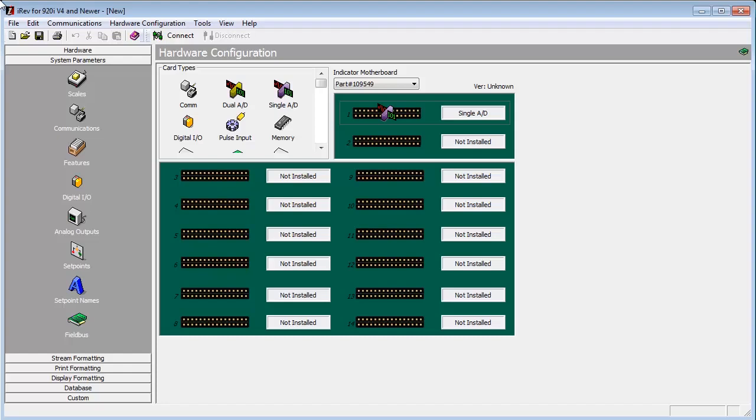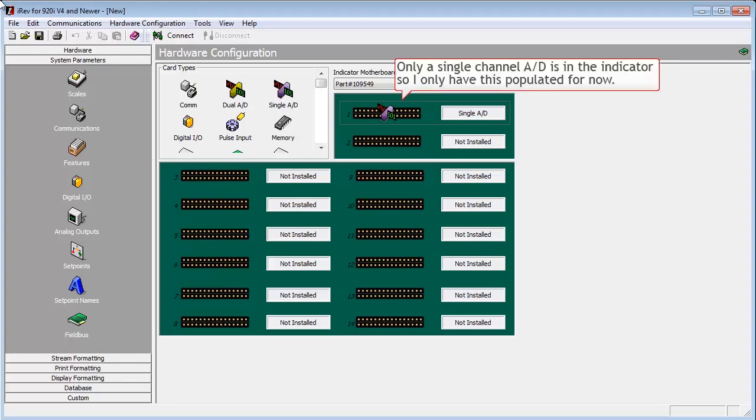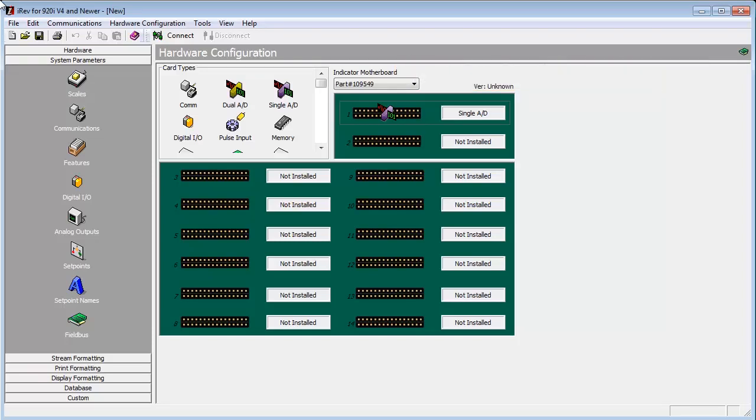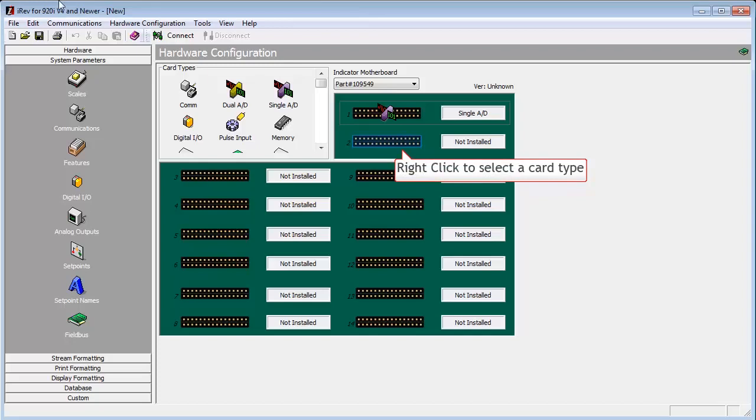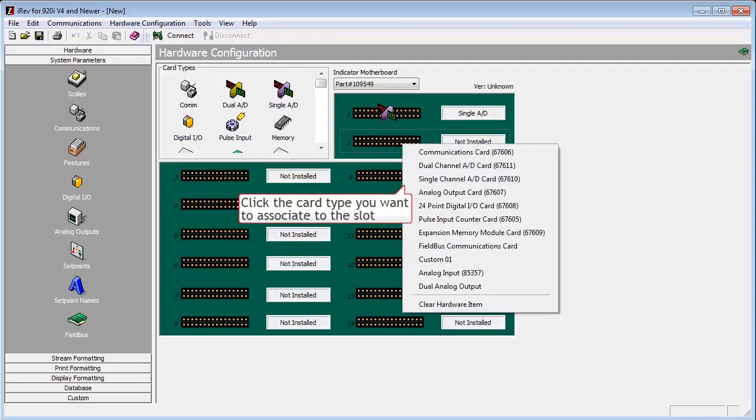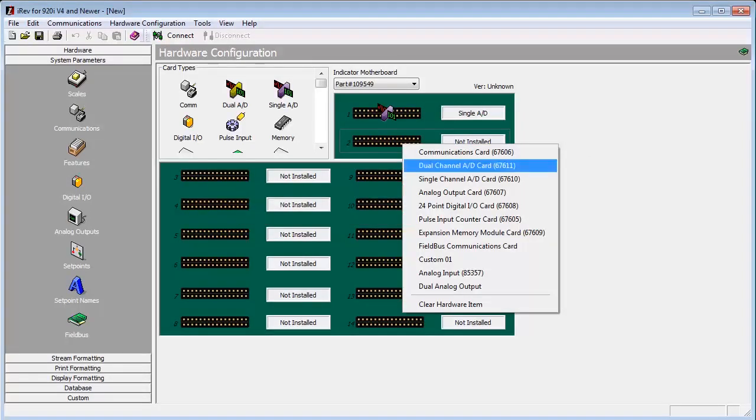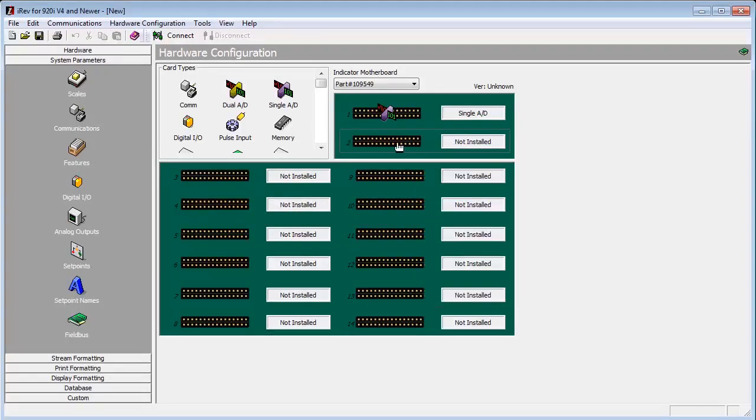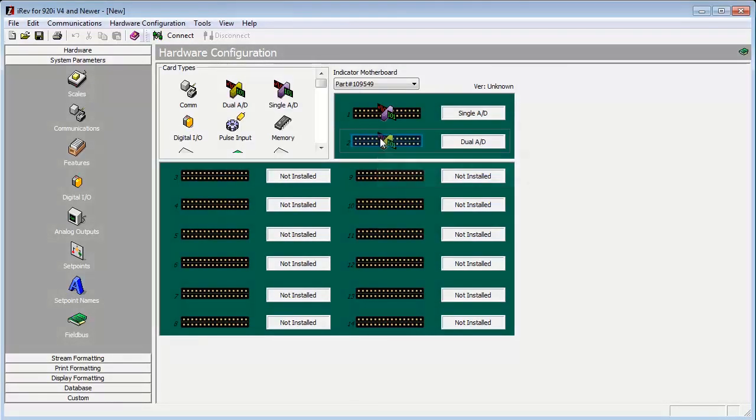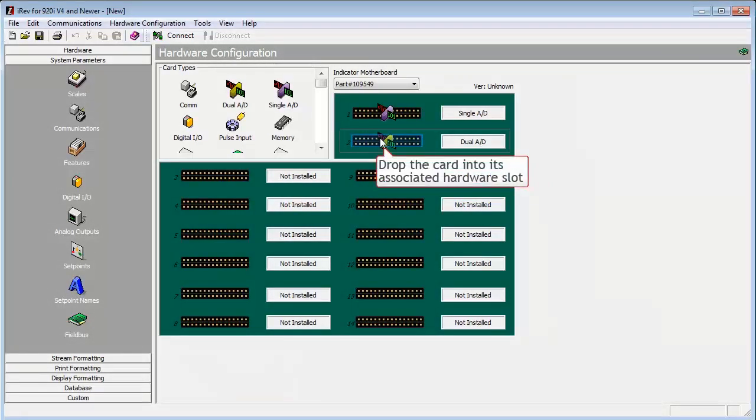As you can see, based on the hardware configuration, I have a single channel A to D in slot 1. If you need to add additional hardware to match what is in your indicator, you would do so by either right clicking on one of the slots to select a piece of hardware, or we can drag one of the options from the card types box down to the hardware setup area.